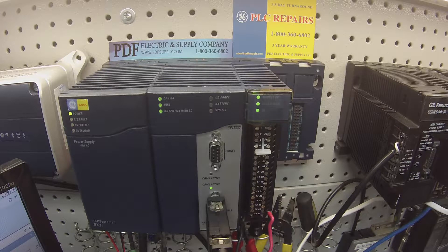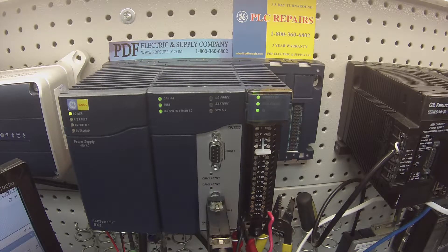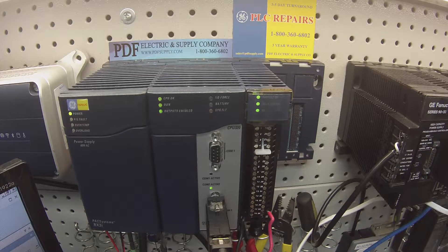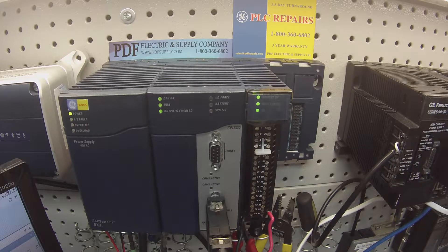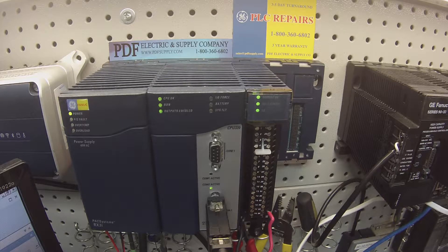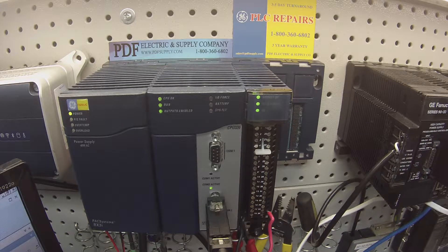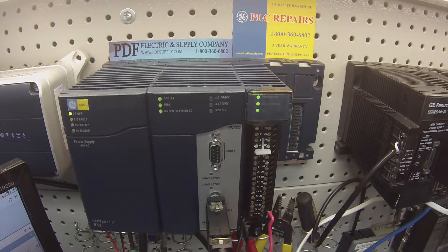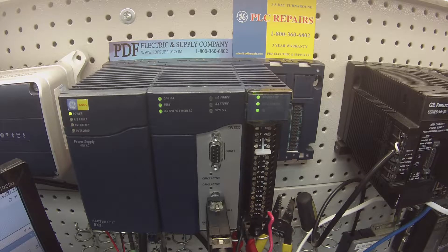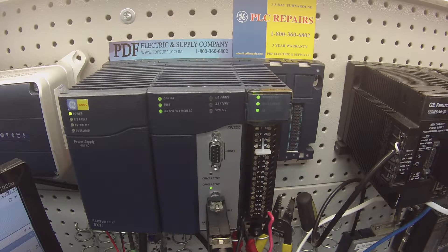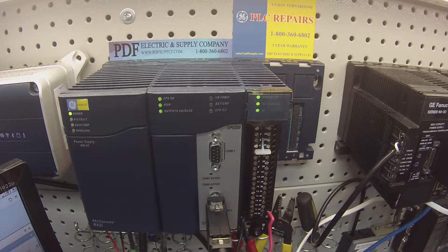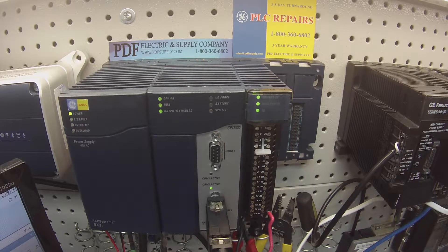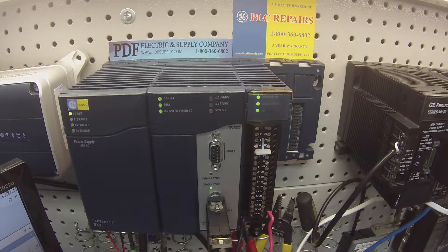So what you would look for in this particular case is that if you drop down to a value of 5,000 in Proficy Machine Edition, then you should get a voltage of 5 volts. If for some reason it's still reading 10 volts, that's a failed circuit. If you drop it down to 2,500, it's still reading 10 volts. Same thing, failed circuit. So note that sometimes these analog cards fail in the state of full value, is what we actually commonly see here.